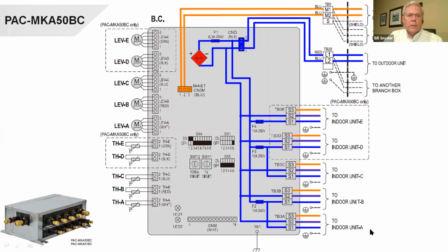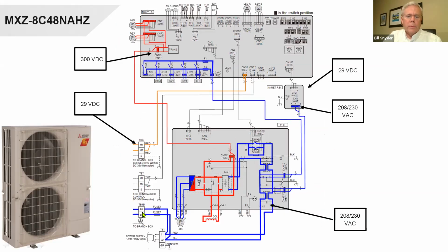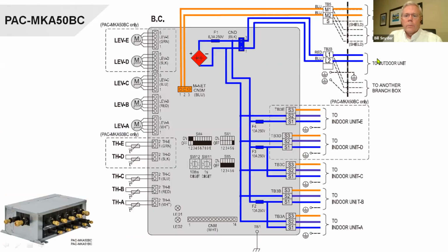Okay, the next is the branch box. This is where the 16 gauge twisted shielded pair comes in and lands on the branch box. It comes down here, that's the MNet. And back from these terminals here, this B1 and B2 comes in right here to this terminal block. So there's your line voltage going in. We do convert to some DC here. We're going in AC, and there's a DC that's not really shown here, but we know this is a DC signal here, and this is a communicating DC signal between S2 and S3.